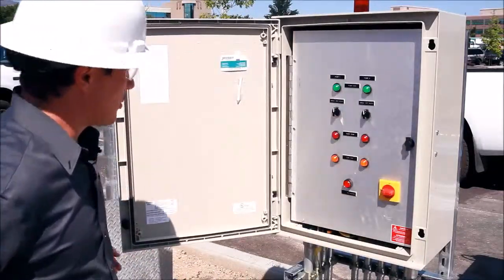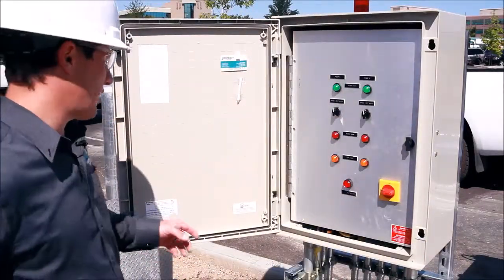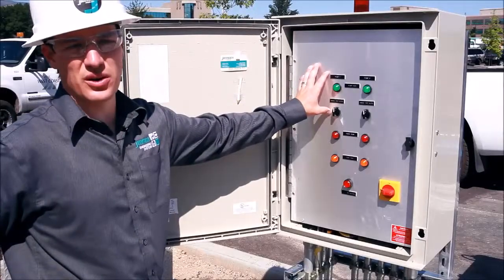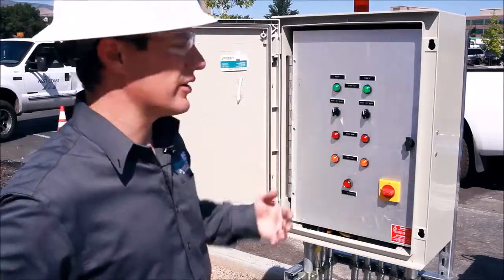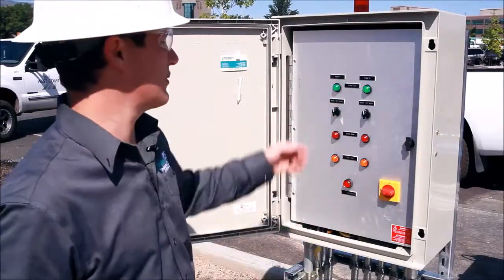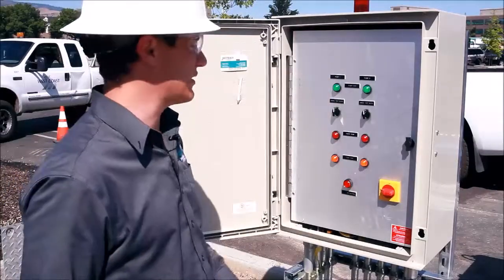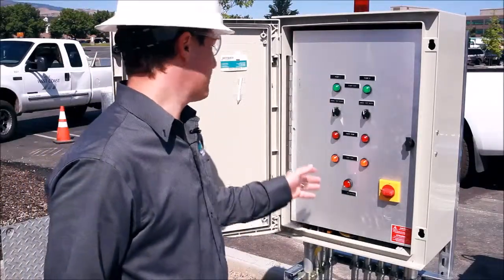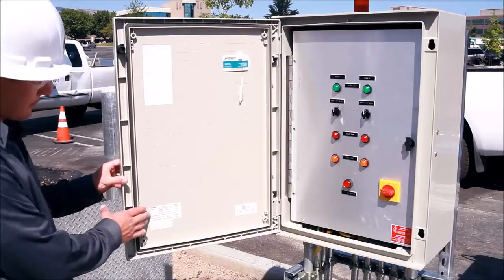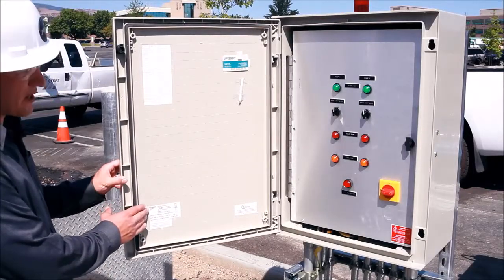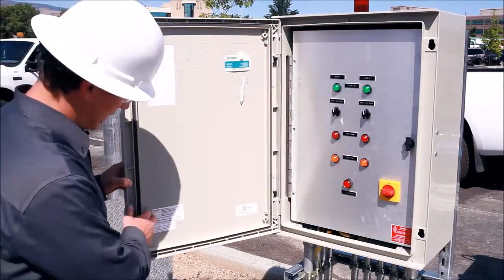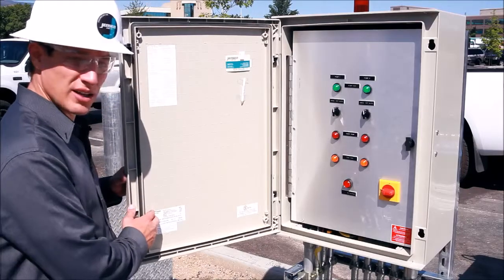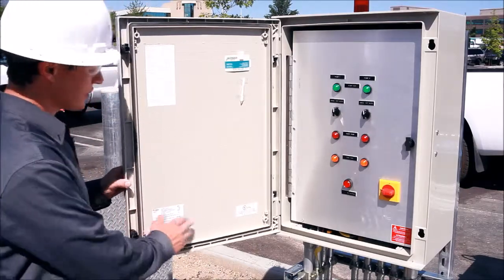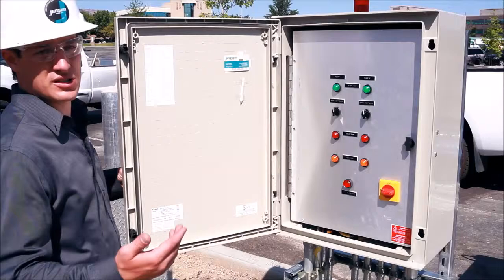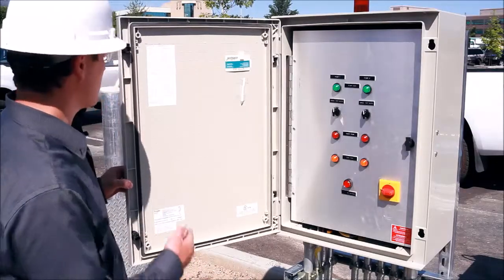So when we first enter the control panel, a couple things to take note of. First off is our stainless steel dead front door. This is to protect any operator or maintenance individual from any damaged internal electrical components behind the dead front door. Off to my left here, you'll notice some of the specifications related to the control panel as manufactured by Reno Controls. Serial numbers, voltages, amps, those sorts of things.